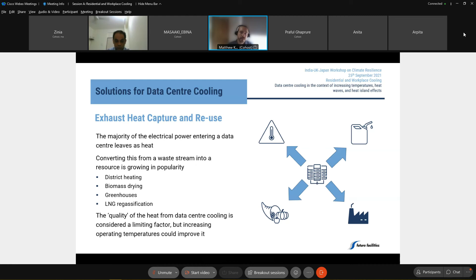But most of these have been trials or experiments, and often the quality of heat is a limiting factor, which is to say we have heat being transported away from data centers in relatively high volumes of fluid, but at relatively low temperature, where typically high temperatures and lower volumes of fluid would be preferred. That's basically because higher temperatures mean there's a better temperature gradient available for the processes you might want to reuse the heat in. So actually increasing the operating temperatures in data centers could make the waste heat more useful.